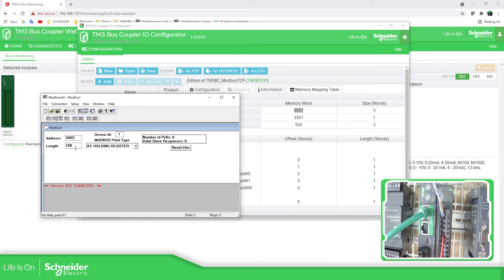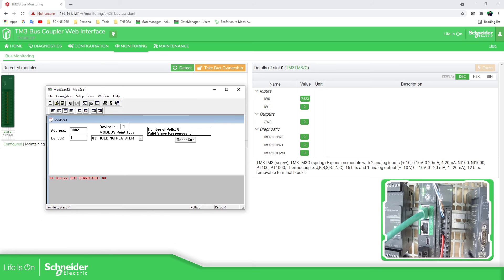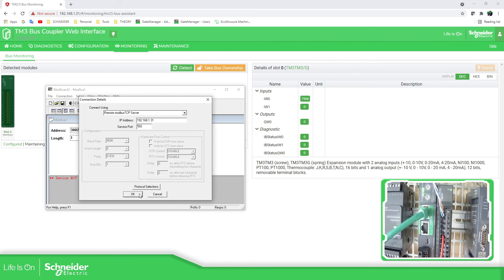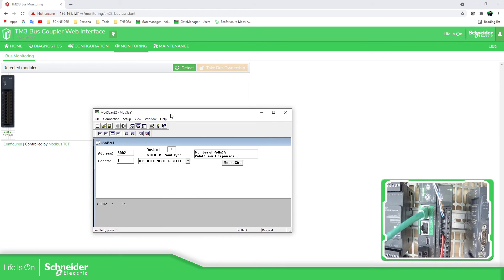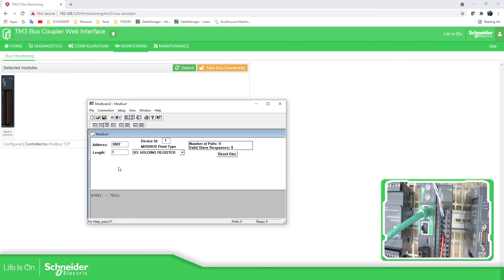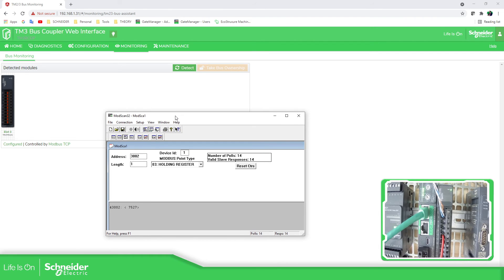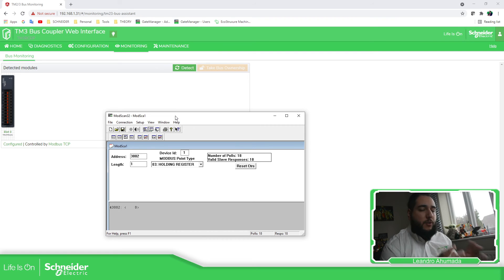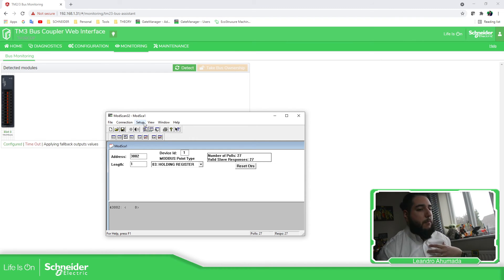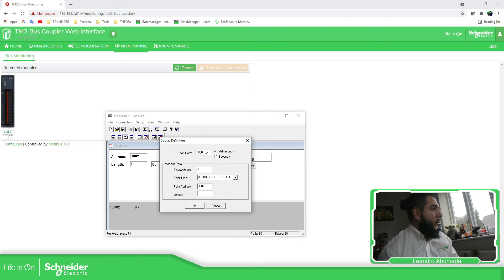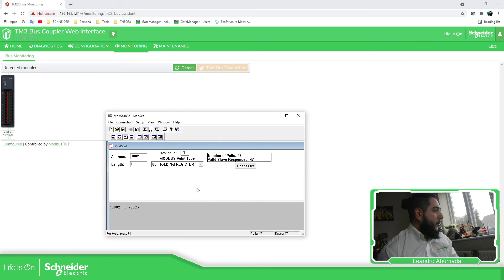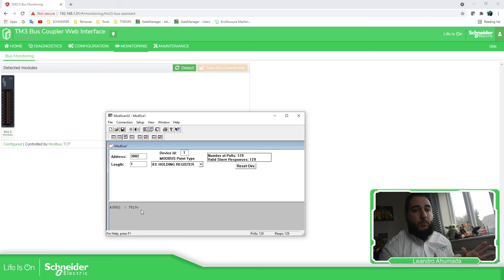In this case, we need to add one to the address. Here I'm going to read one register. I need to identify the device. Now I should be able to see some information. Here is something important: you can see the information I'm reading is blinking, and that is because of the timeout. The master device or client asking for information needs to read more quickly. If I change the polling interval to, for example, 100 milliseconds, you should be able to see the information clearly without the blinking values. That will solve the problem in case you have this issue.